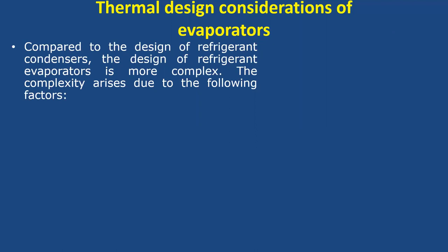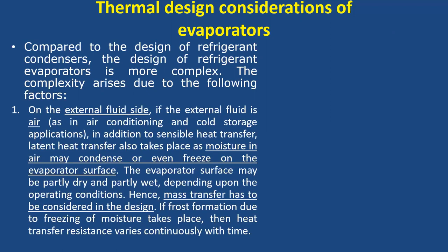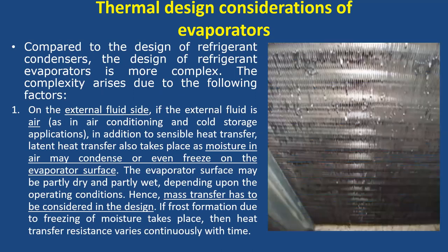Because what will happen, the complexity of the design arises because of the following. Generally on the external fluid side, if the external fluid is air, that mostly happens in air conditioning systems or cold storage. In addition to sensible heat transfer, latent heat transfer also takes place, as moisture in air may condense or even freeze like this on the outer surface.